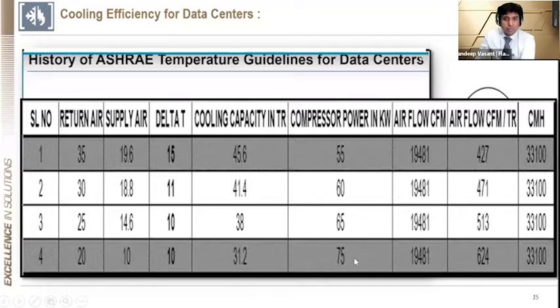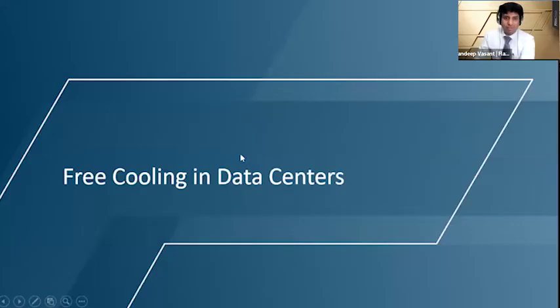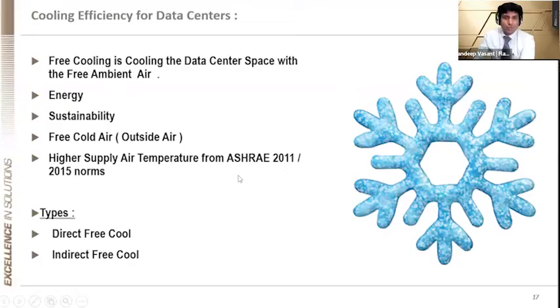Thereby, simple math: if you run the unit at a return air of 20, or the supply air from 10 to 19, you get a power consumption saving of 50%. And the discussion doesn't stop here. ASHRAE says you can still go as high as 27, thereby you get a good saving. So to niche down on free cooling in a data center, what is free cooling?